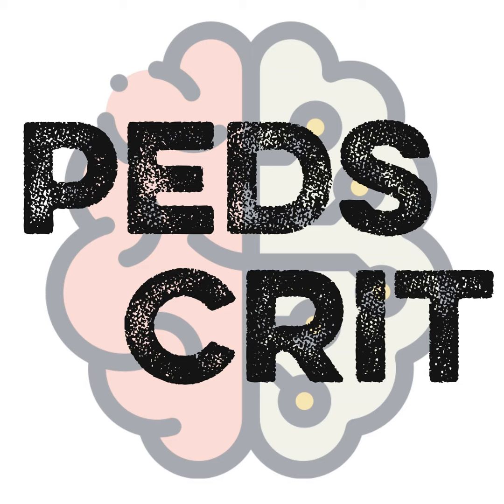Since trigger asynchrony is the most common, it might be a good time to jump into the different types. We've already mentioned that pressure trigger is less sensitive. And if we have a trigger that's not sensitive enough, we might have a missed trigger breath. So tell us more about that. Yeah, so missed trigger is certainly one of the more common ones as we talk about infants particularly, and a lot of our infants who may be weak, whether it be neuromuscular weakness, whether it be myopathy from being in the ICU or other causes. They may not just be strong enough to trigger the ventilator because our sensitivity is not set the right way.